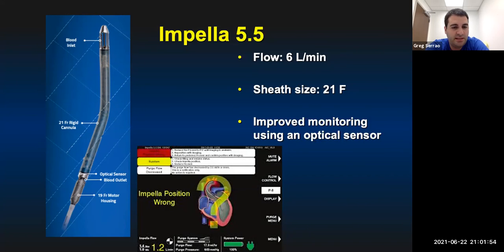So with the addition of this optical sensor, the device does a much better job being able to tell where it's positioned and if it has migrated, and alerts you very quickly if that has happened, and tells you how to fix the device based on the way the migration has happened. Either has it been pushed too far into the ventricle, has it been pushed or pulled too far out of the ventricle, and it really makes ICU care a lot better.